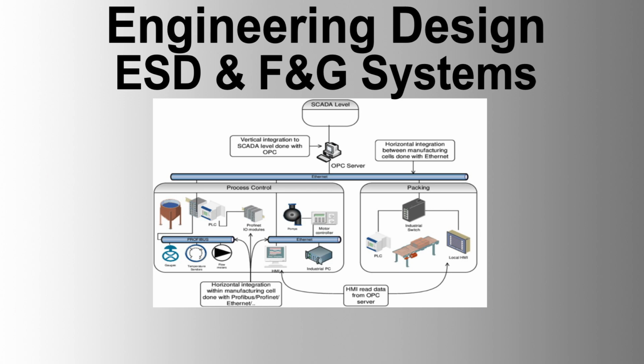3. Graphical user interface. The software must include a user-friendly graphical interface for system monitoring and control. The GUI should display real-time data, system status, alarms, and events. Graphical representations of the plant layout with clear indication of sensor locations and statuses must be included.